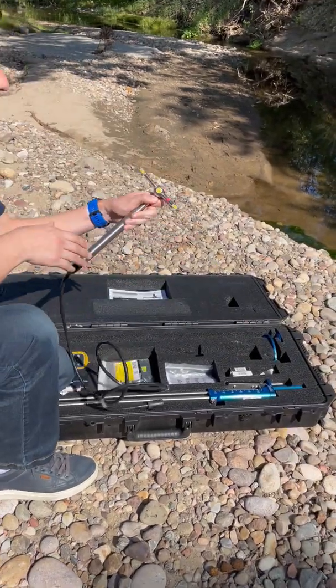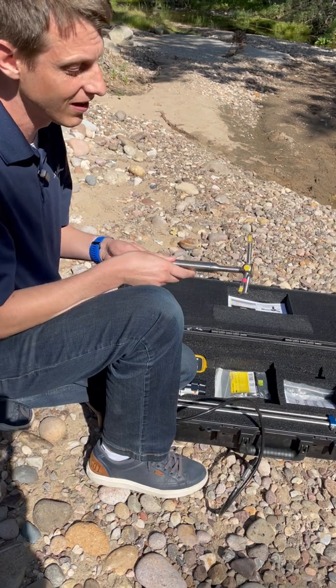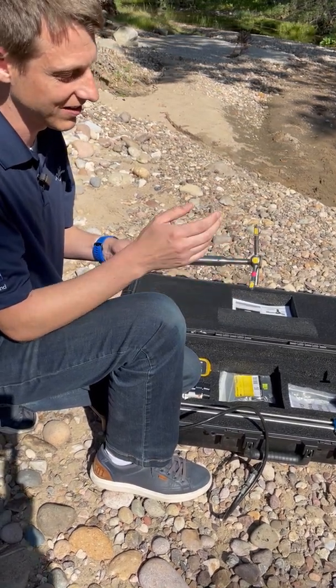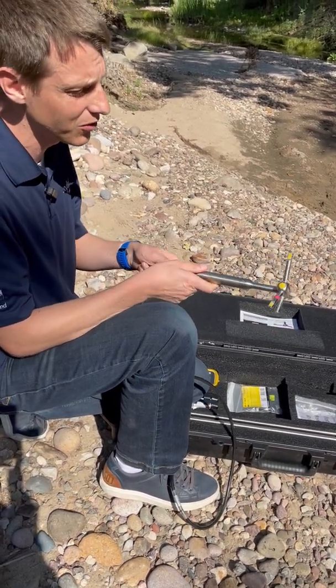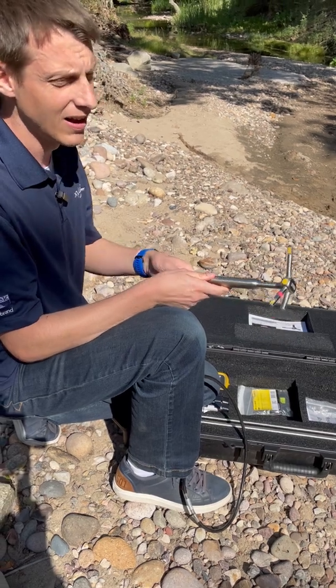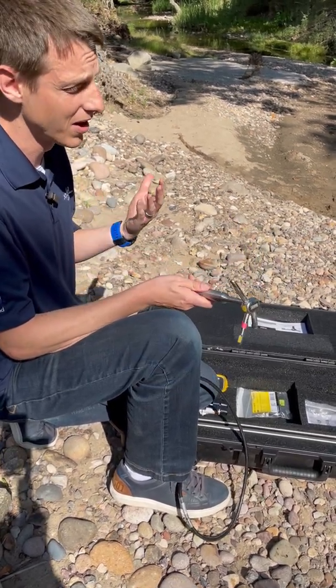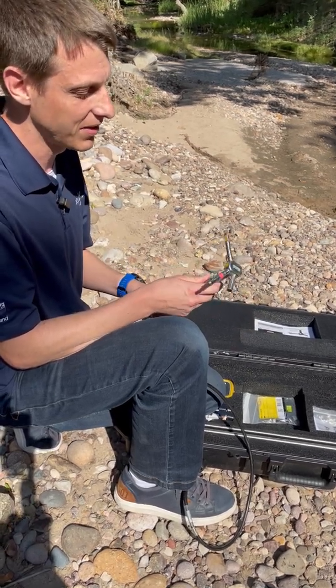In here we have our Flow Tracker 2 probe — this is really where the work happens. You can see our acoustic transmitter and our receivers that measure the velocity for us. The Flow Tracker 2 is our acoustic Doppler velocimeter. You may be familiar with the original Flow Tracker — it's one of the best sellers we've had at SonTek — and this is our updated version.